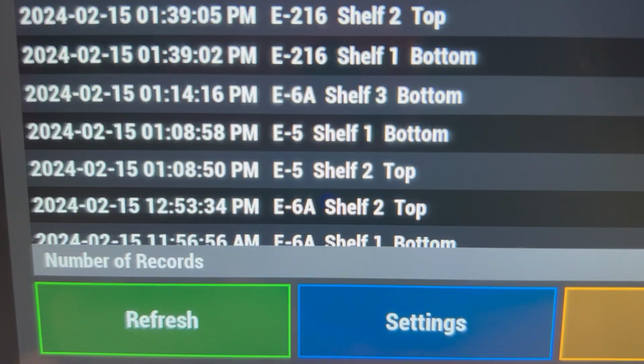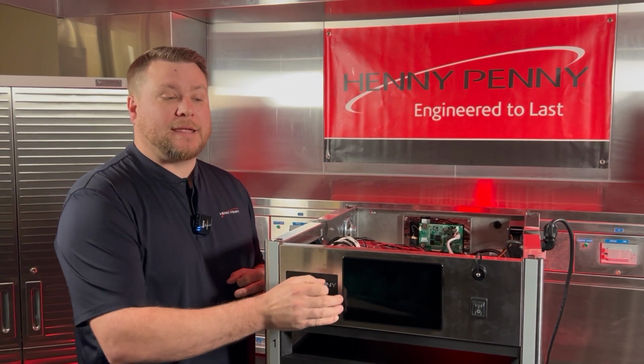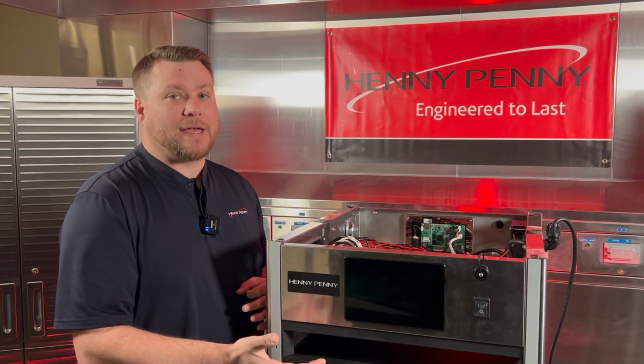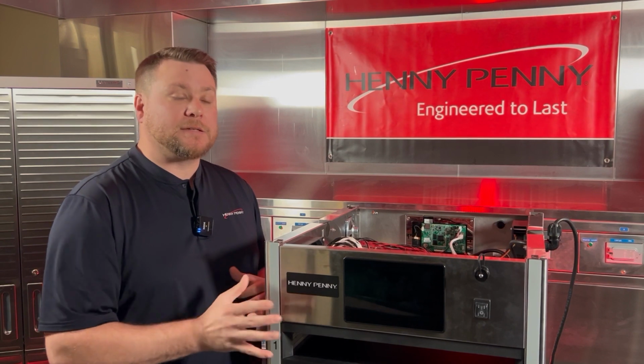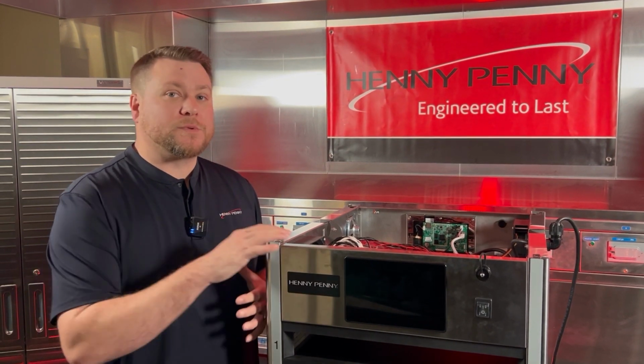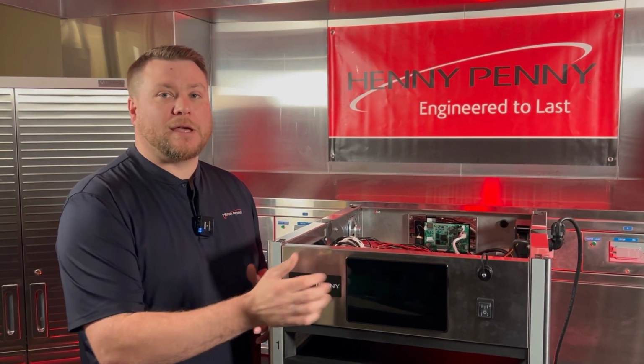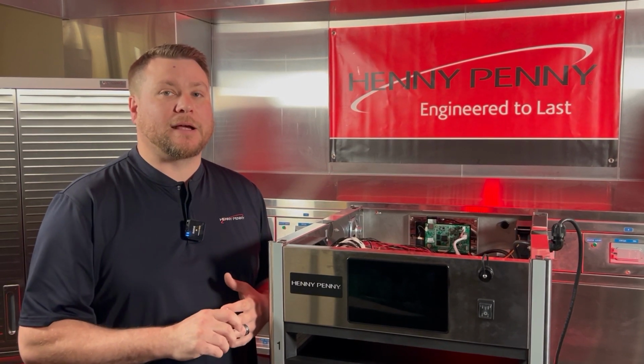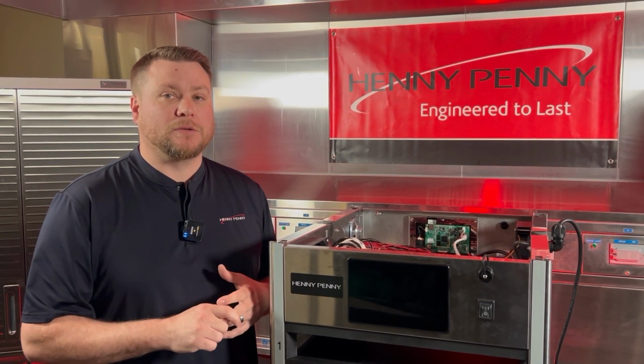Remember, the heater that has failed with that E-6A will tell you which heater it is in the error logs, like we've talked about on some of the other error codes. With it doing that, it will also go ahead and disable that heater from being available until that issue is resolved. Once we resolve that issue, we can go back in and turn that heater back on so we can continue to use it.